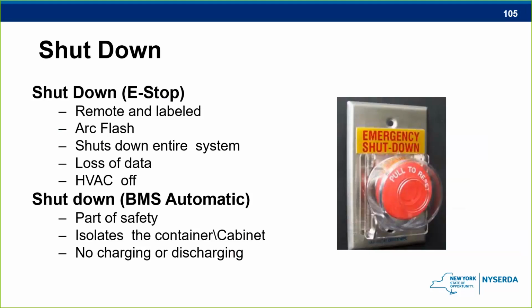So something that you need to be concerned about is, if they did shut it down, that BMS that they're trying to collect data from, they're trying to figure out where there is a trending rising temperature, let's make sure that that emergency shutdown doesn't shut down that data, because that's something that they may utilize later on to figure out whether we have a trending temperature where we have a thermal reaction taking place and it's continuing to go, or if it is actually something that did take place and now this thing is running normally. So again, interpretation of the data from that battery management system, the eyes and ears, is going to be key for some incident commanders moving forward.